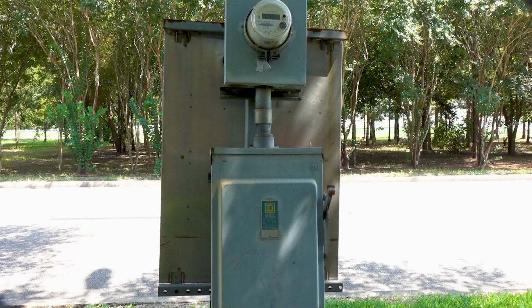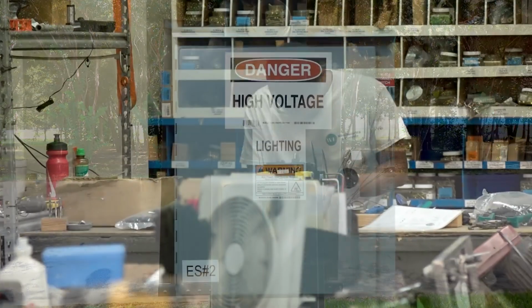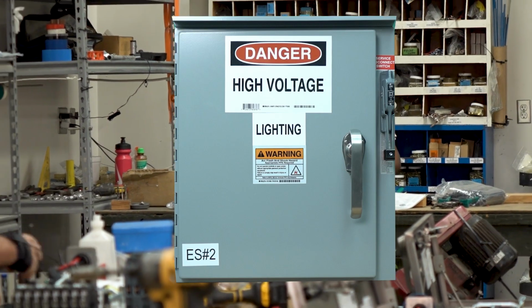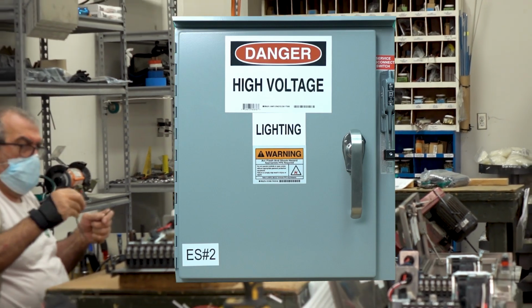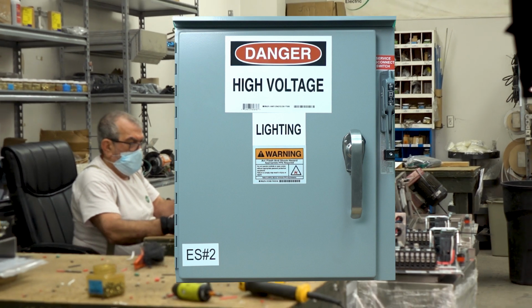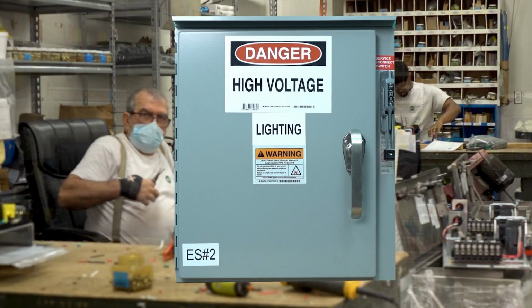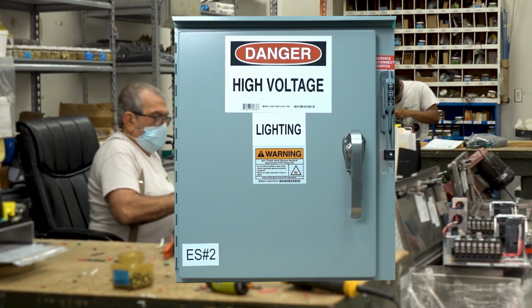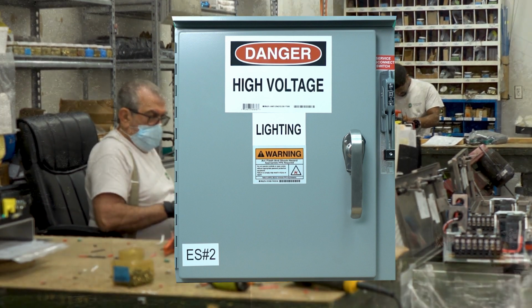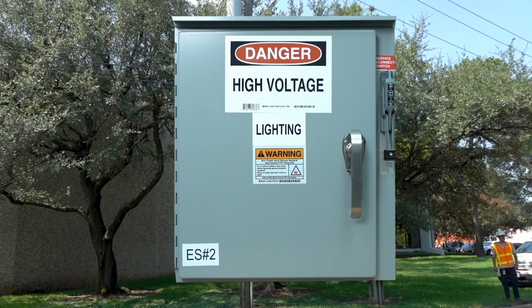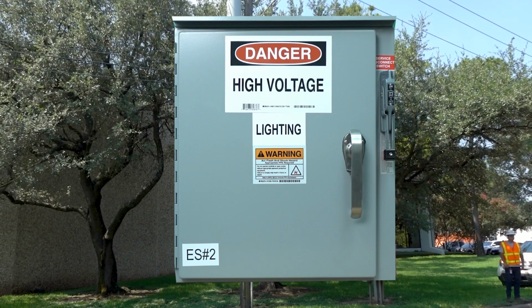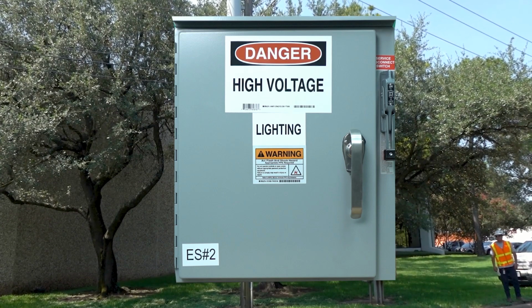The enclosure is properly secured. The enclosure is properly marked with the danger high voltage and flash hazard label. There should also be a label which shows the type of load served and a label with the unique identification name of the service on the enclosure. The unique ID on the plan sheet's data chart should match the identification label on the enclosure.